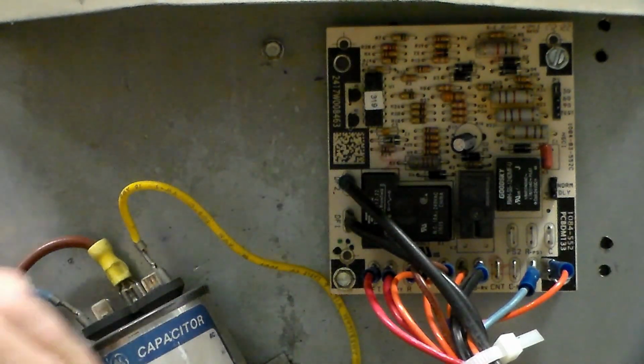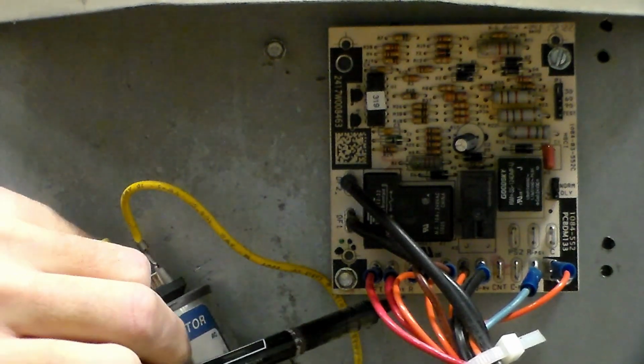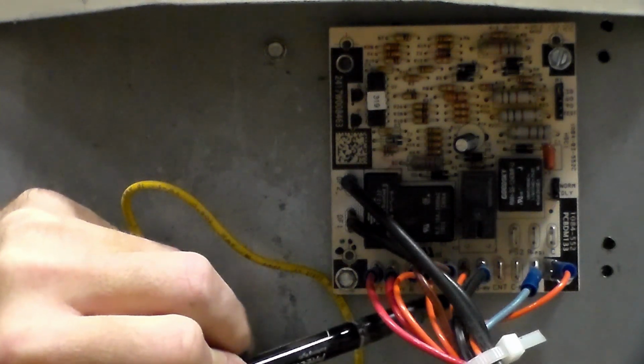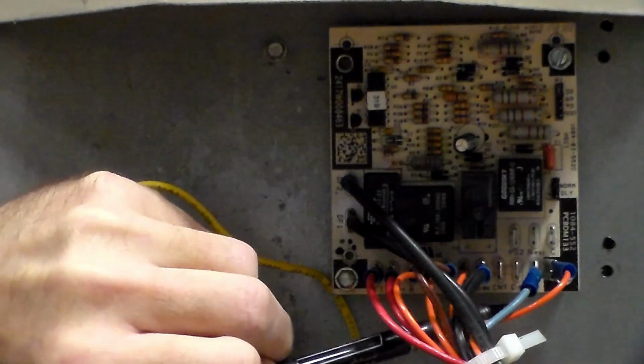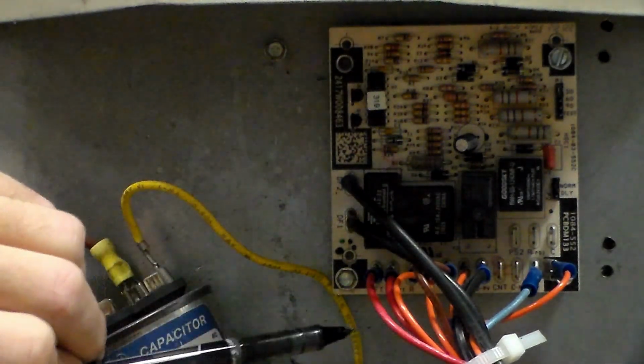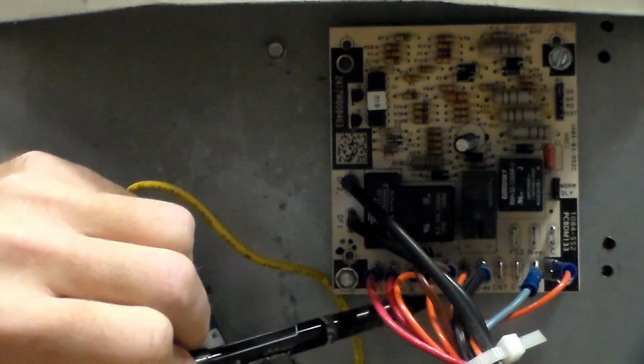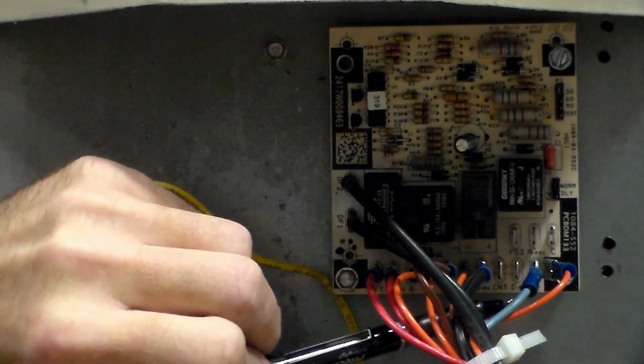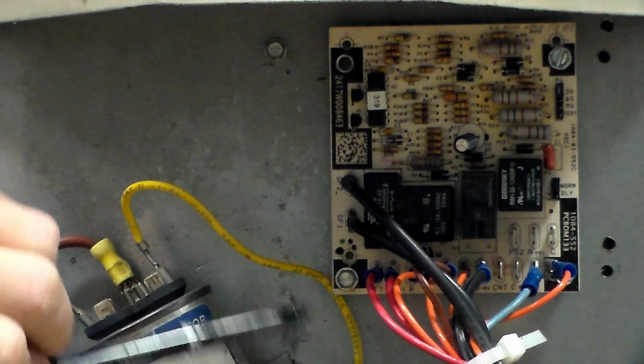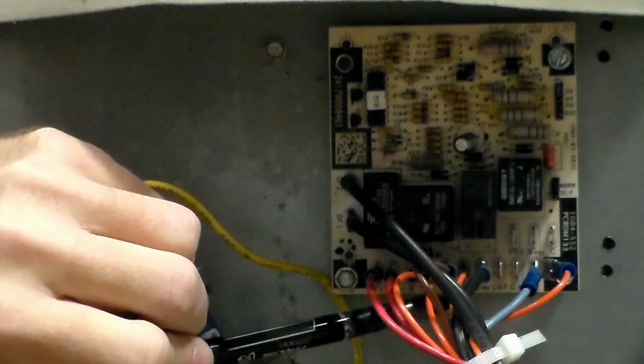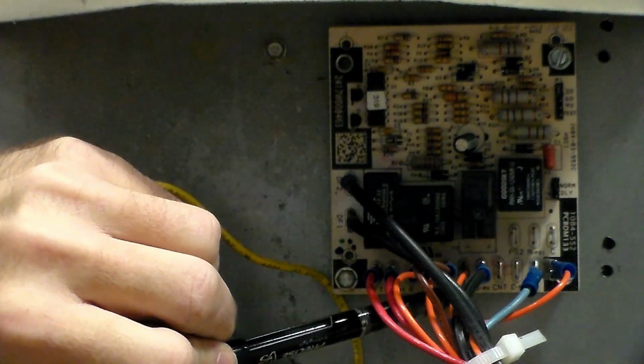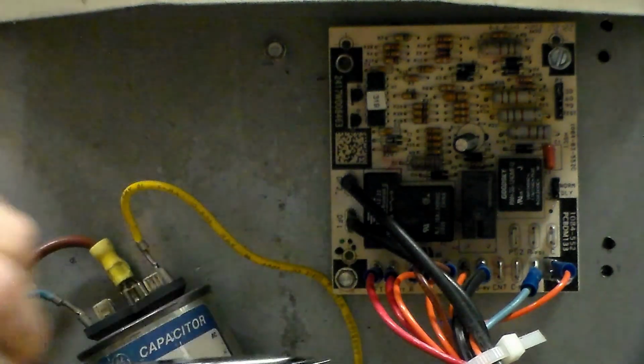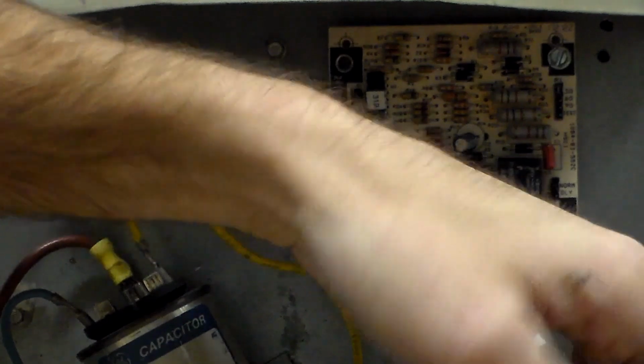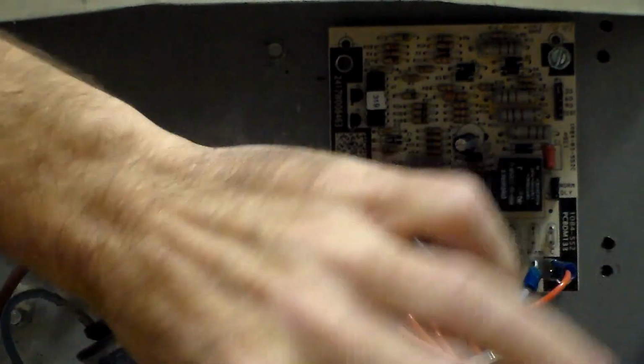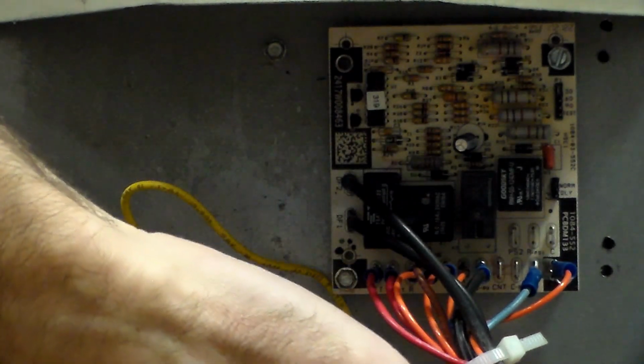And then underneath, I got R and W and Y and O from the thermostat, just like I would normally have. And then I have C from the thermostat. It was hard for me to get my camera in here for you guys to see that, so you just have to take my word for it. We got R, W, Y, O, and C from the thermostat, just like any old heat pump. What this one's doing a little bit different is it's got O out. It's got an O with a little RV next to it, and it's sending power out of that terminal down here to the reversing valve coil, and then it's coming back just to common on the contactor.